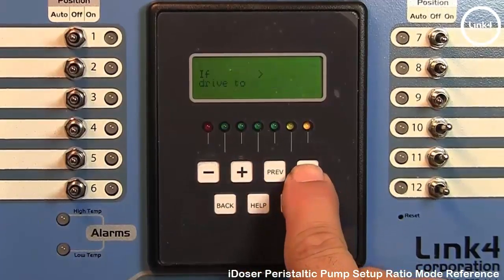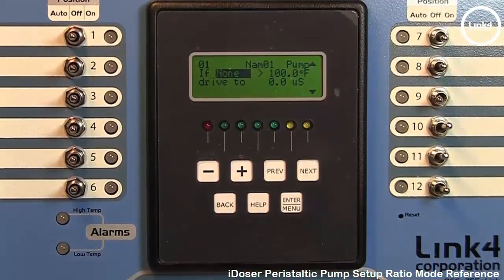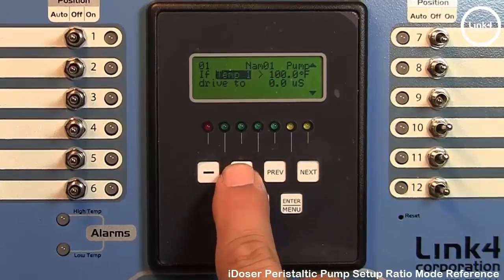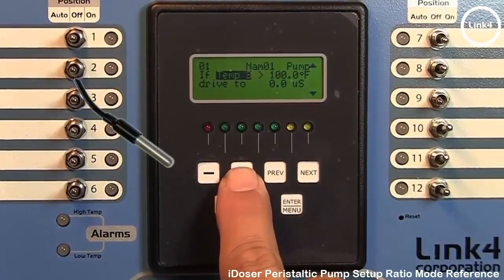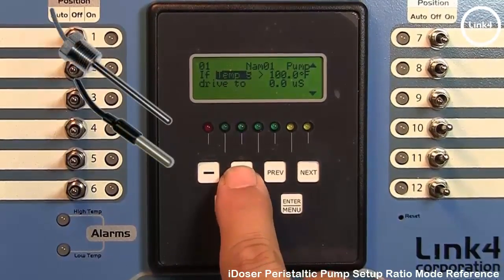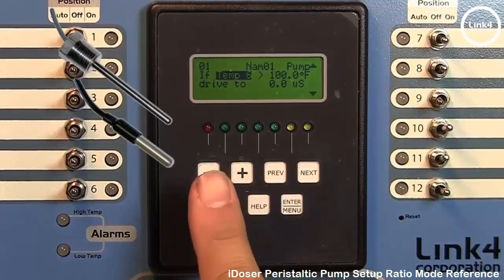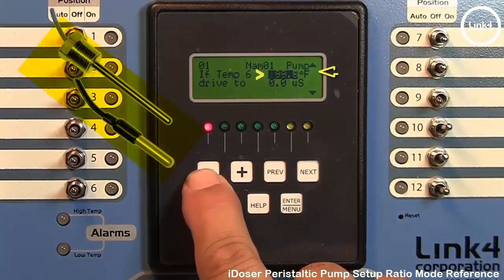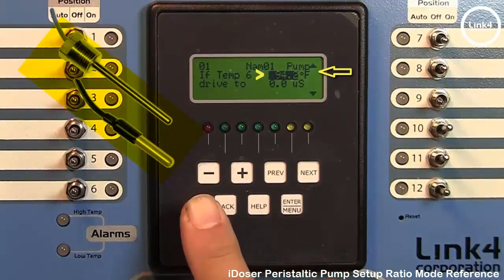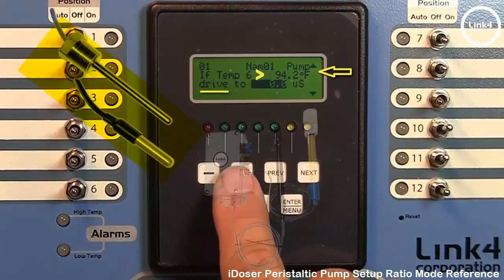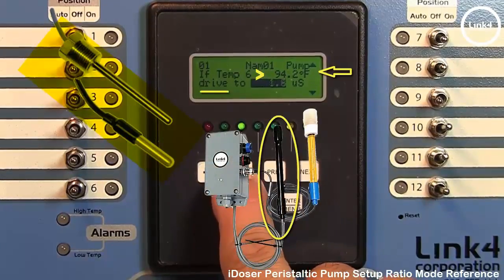Hit next. Now here we have a temp override that you can program. So if temp probe 1, 2, 3, 4, or one of the probes you have assigned in this field is above a certain threshold value, let's say 94.2, drive the EC probe to a certain value in microsiemens.